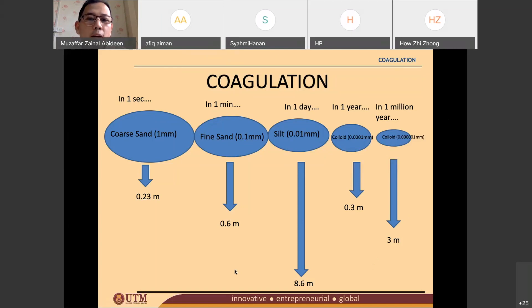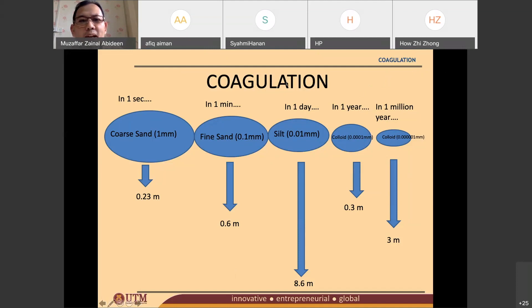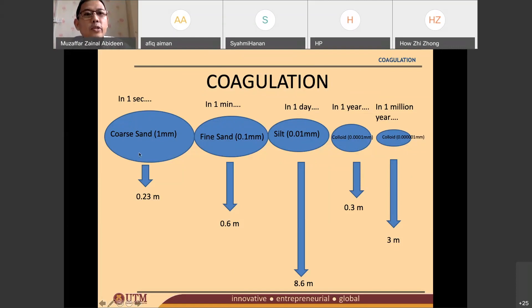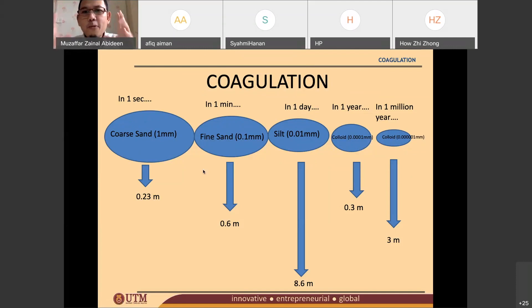So what conclusion can we make? The smaller the particle size, the longer it takes to settle. So what we want to do is form very large particles, so that they can easily be removed. That is the purpose of coagulation — forming smaller particles into greater size particles so that they will go down very fast.